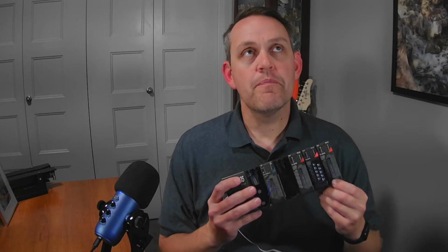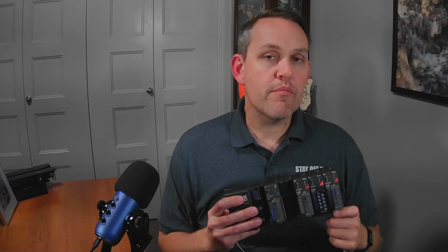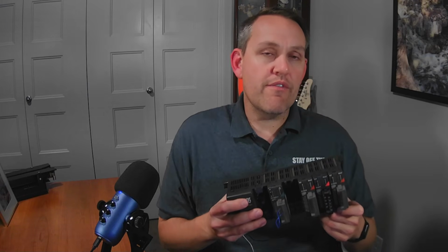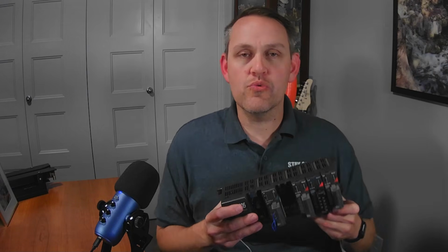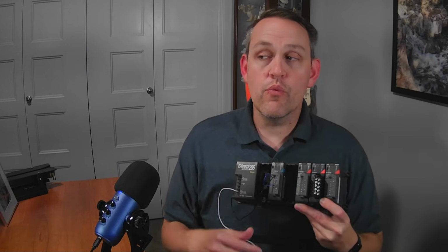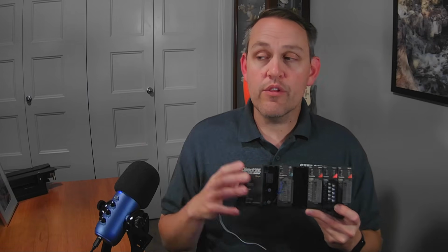So for instance, if we were running the ride and I said, hey, what happens if I turn, let's say I put a bunch of booster motors on the track and I monitor their speed. And it's very critical that while the ride is running, those booster motors don't run. So I want to test my program and see if it works. How do I do that? Do I just wait for the thing to fail? No, I can't wait for the thing to fail. That would take too long and it might not ever happen. So what I do is while the thing's running, I go into my output modules and I take one of the booster motors and I force the output on, which forces the booster motor to come on out there. And then what I look for is I look for my ride to fault out. And it says, yep, there's a booster motor running when it shouldn't be running. That's an example of forcing output.